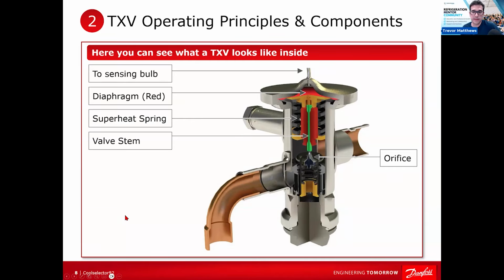The big thing is there's so many DOA TX valves out there, right? We get them all the time, and I've got some good pictures, man. I used to send a ton of them back to the manufacturers in Germany. Every time here in Canada, we're a division of them, they would be like, denied, and then they would send these pictures showing this little bit of debris in there that was contamination, and it's like that's what jammed it up. I talked to all the valve manufacturers, I know all of them, even when I would work for a manufacturer, and it's the same thing.